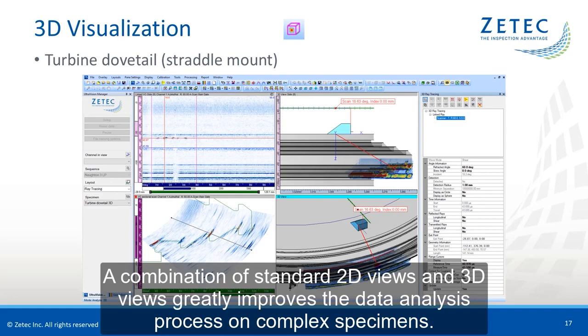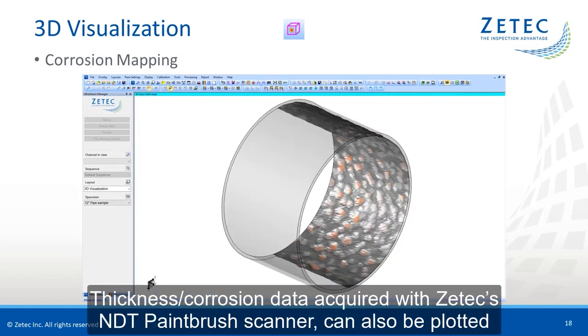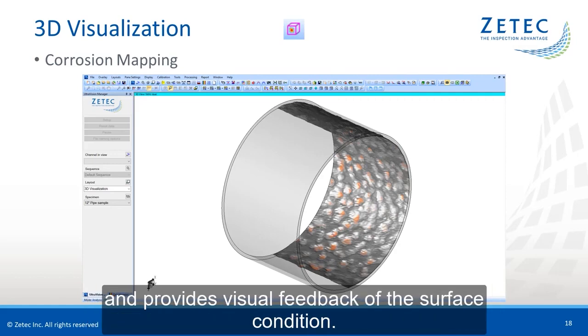The 3D visualization module allows for plotting the data in complex components. The combination of standard 2D views and 3D views greatly improves the data analysis process on complex specimens. Thickness corrosion data acquired with Zetec's NDT Paintbrush scanner can also be plotted and provides visual feedback of the surface condition.